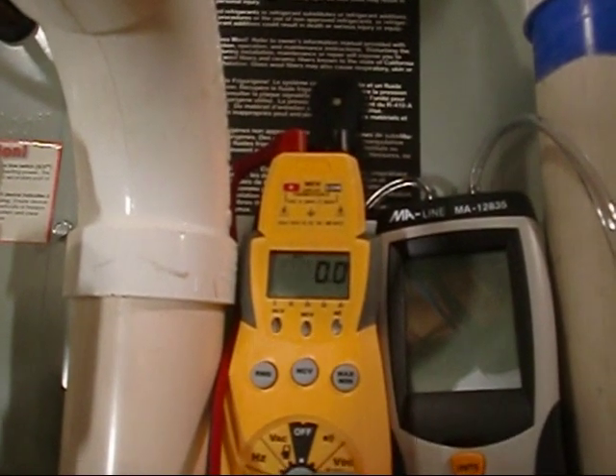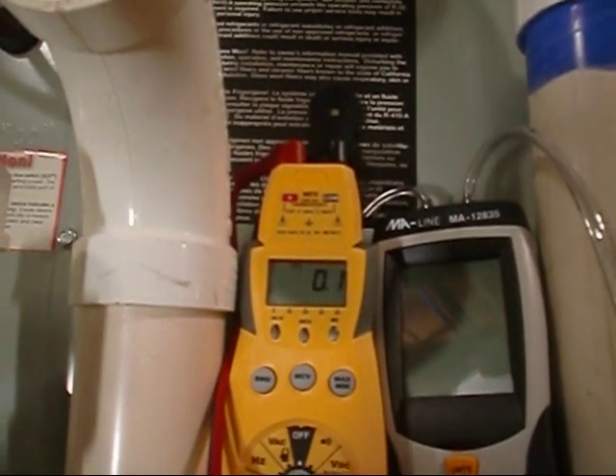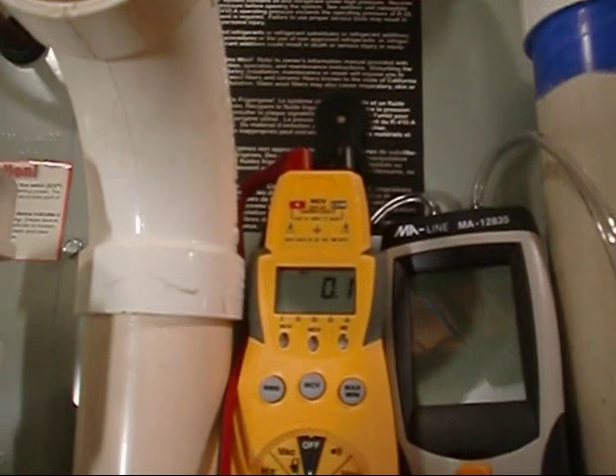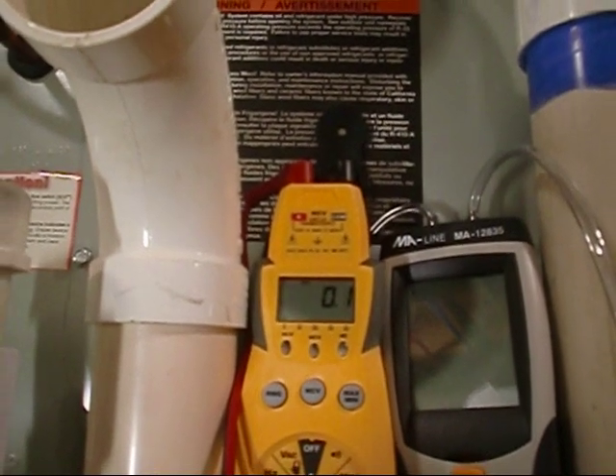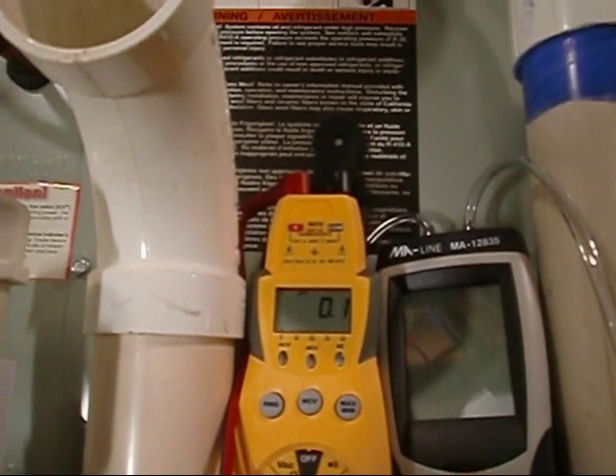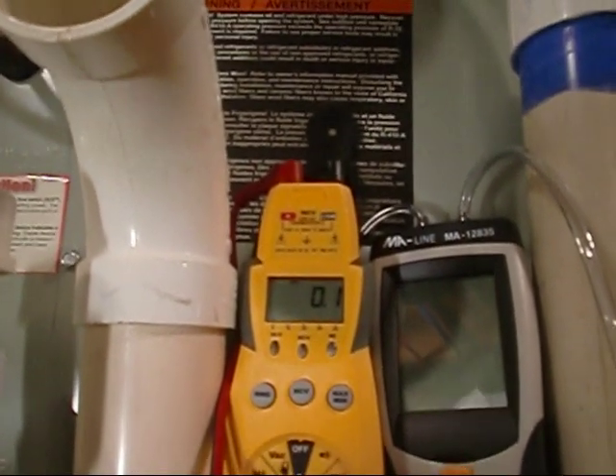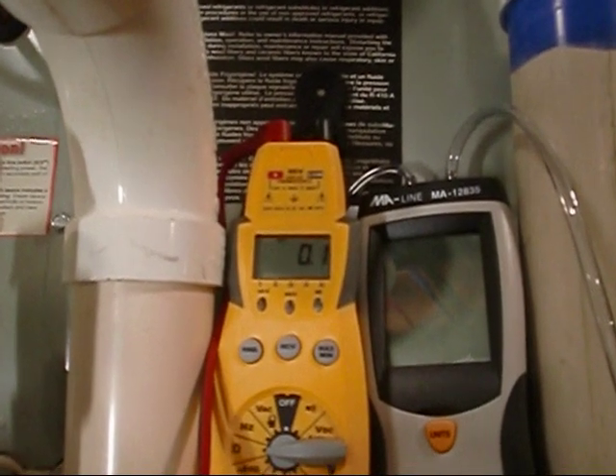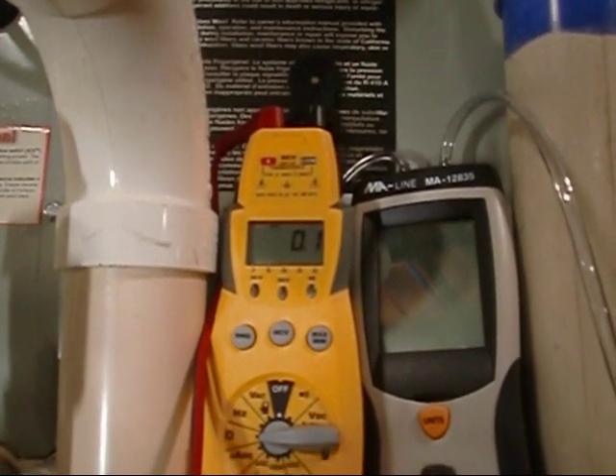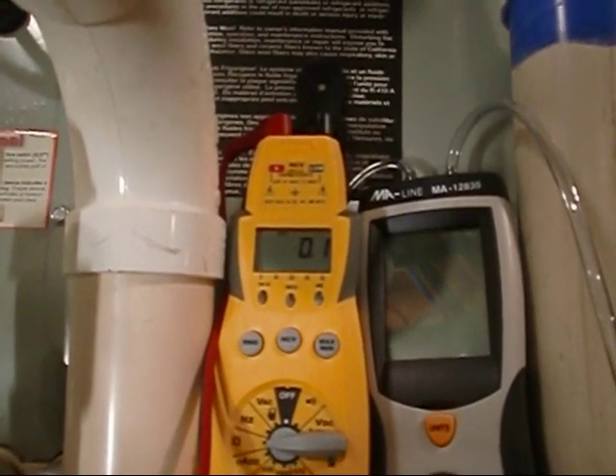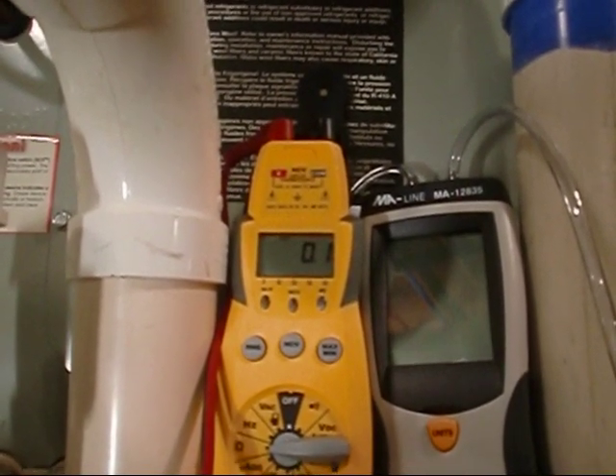She's gone enough, there she goes, she pulled, it got up to enough speed where we're pulling 0.1 resistance. That tells us right there, y'all, that pressure switch is made. Let's get all this stuff hooked up, and we'll get after it.